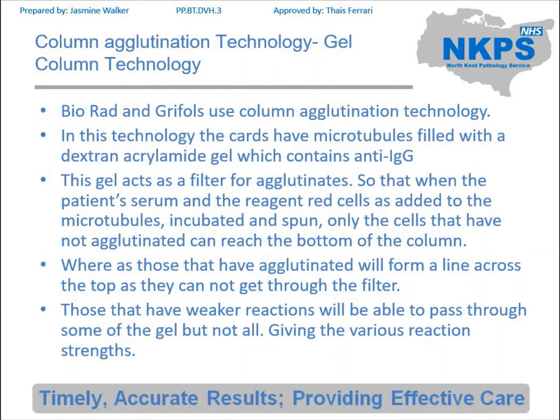The cards will have microtubules in, each with a different reagent. Within those microtubules there is a dextran acrylamide gel which contains anti-IgG. This gel acts as a filter for agglutinates. What happens is you will add in the patient's red cells or plasma and the reagent needed at the top of the microtubule. This will be incubated if required and then spun down. As it's spun it is pushed down into the gel.